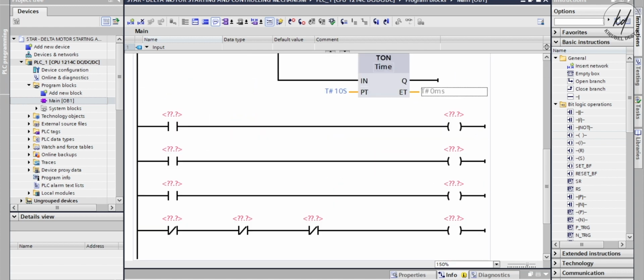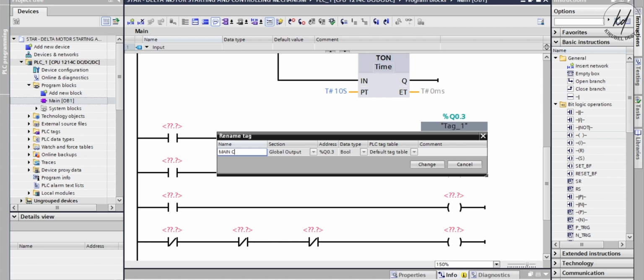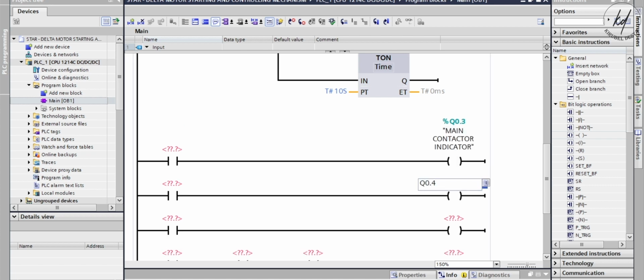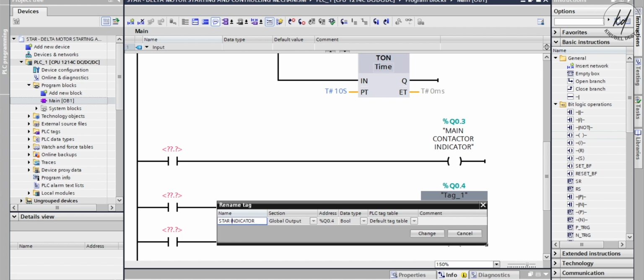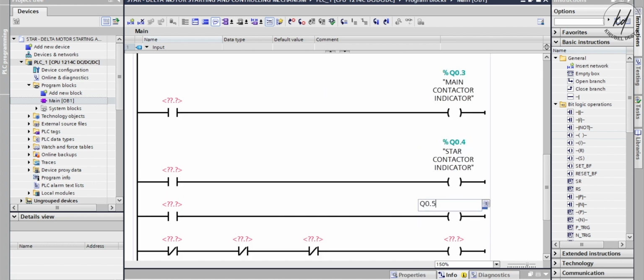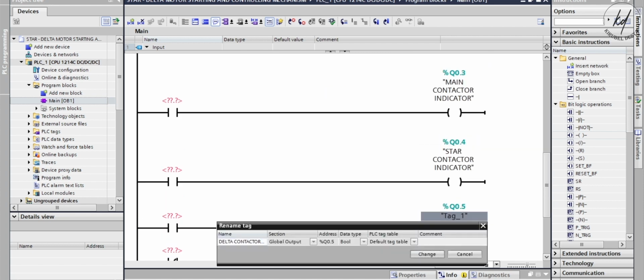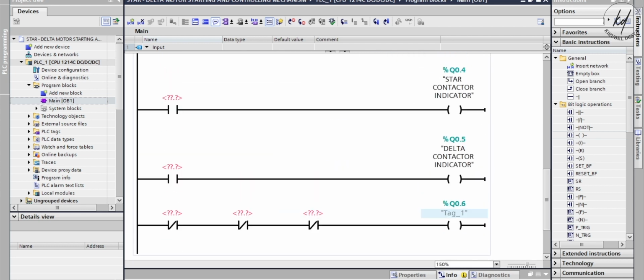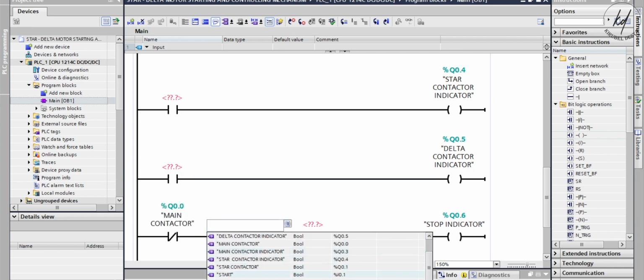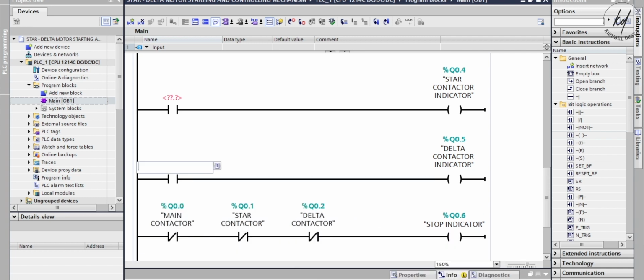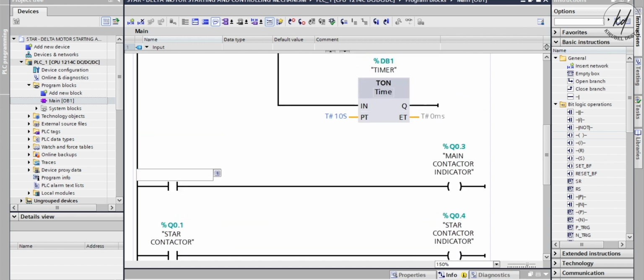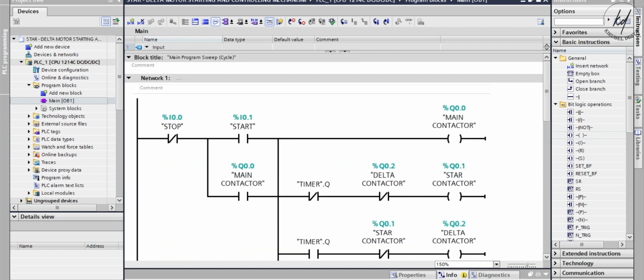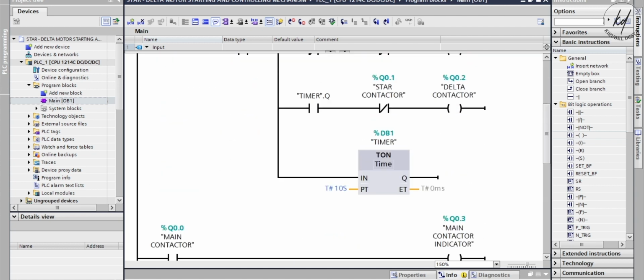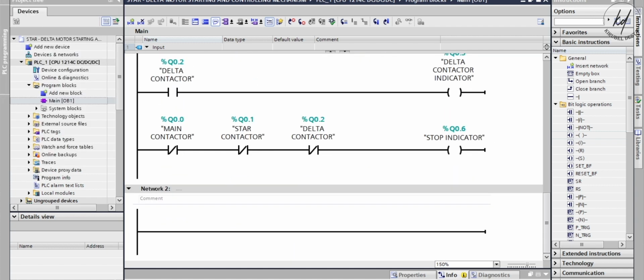Star-delta starter means two separate states of starting. First, the motor starts with a star connection, and when it reaches 75% to 85% of its full load speed, the motor runs in delta connection. When the motor starts without a star-delta starter, first, the starting current would be 4 to 6 times the full load current. Second, an oversized power capacity cable is required to handle the initial high starting current.